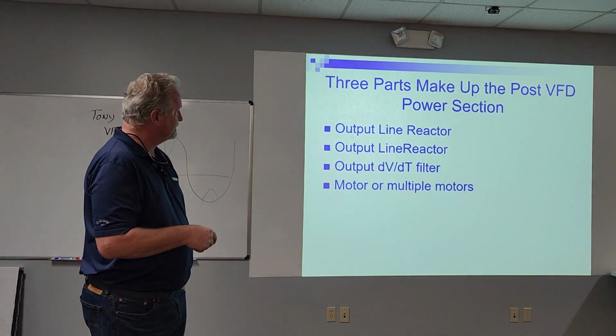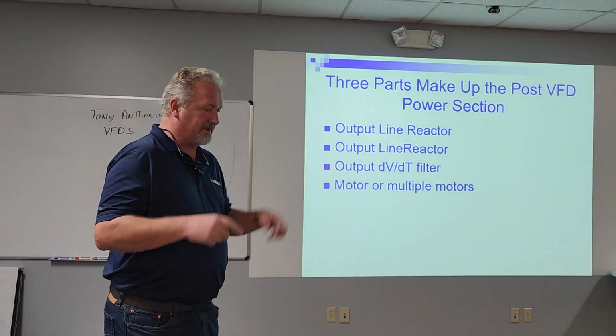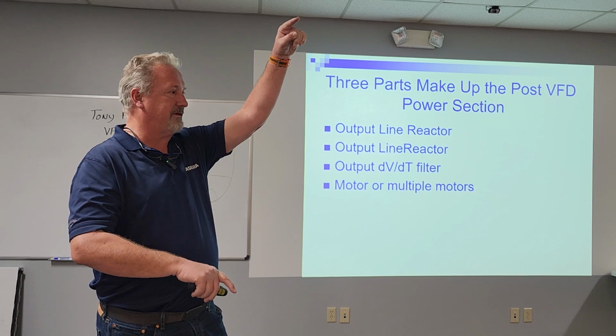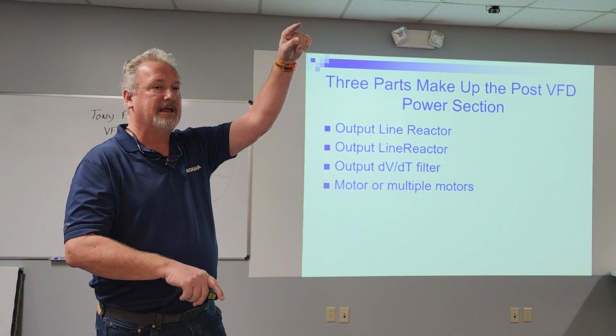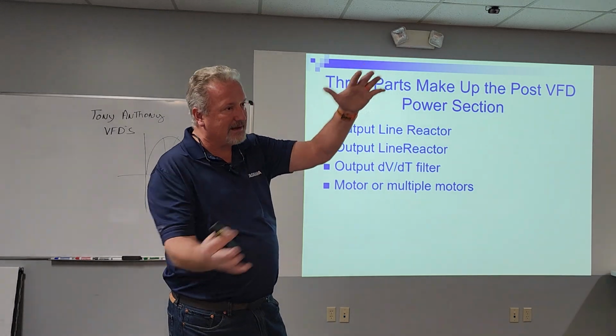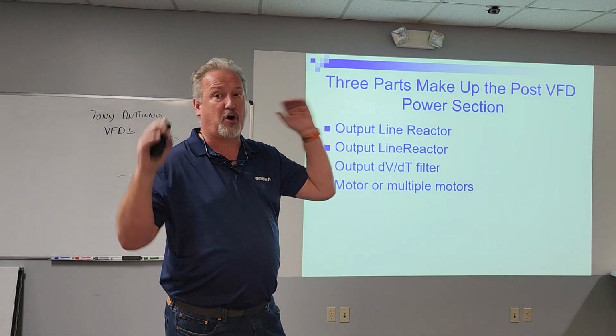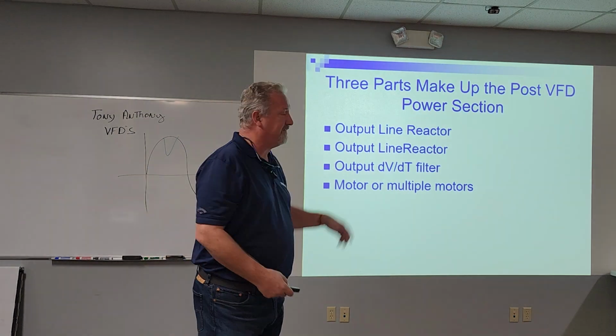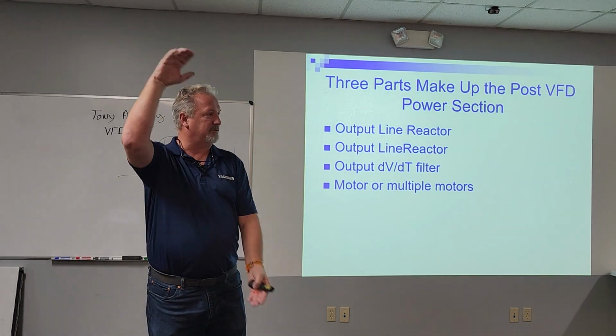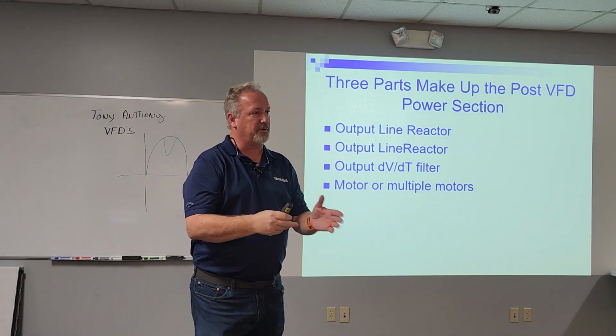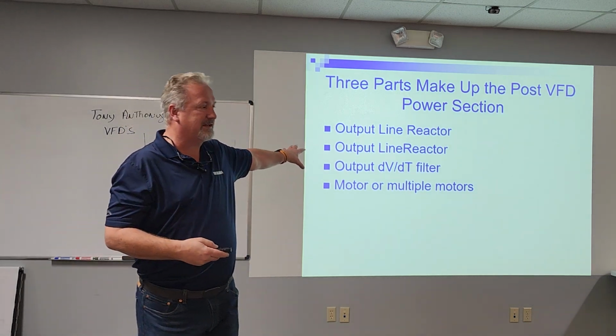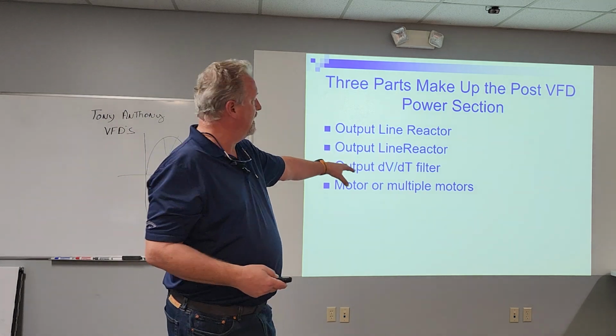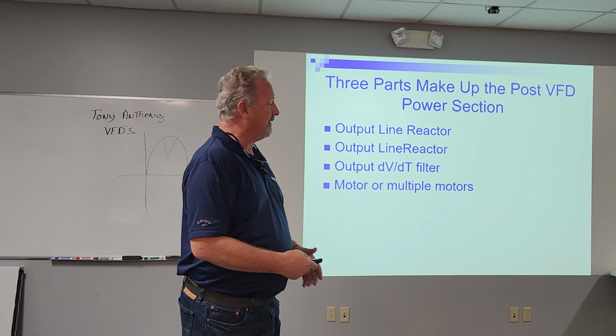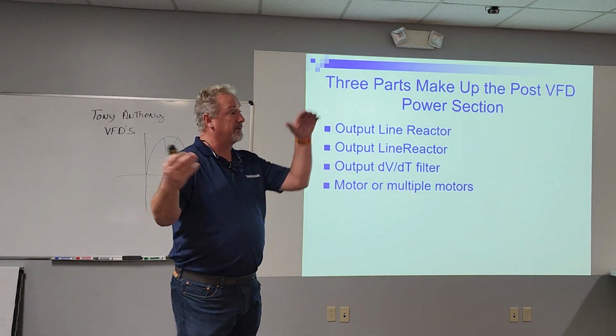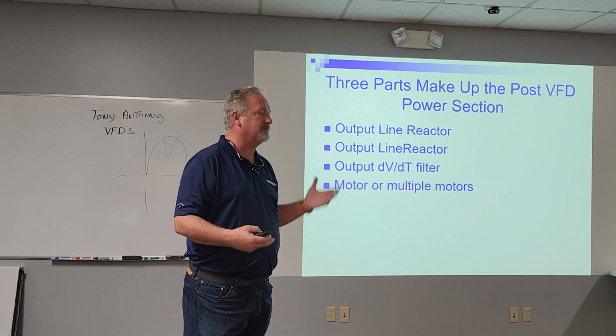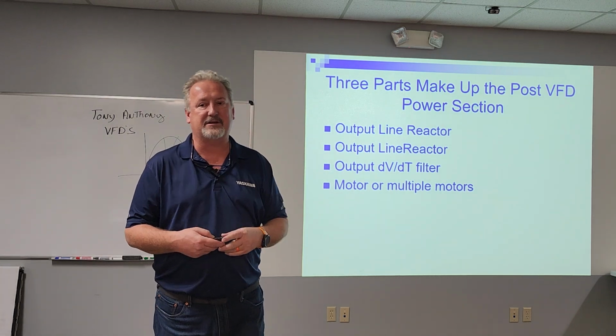We have dV/dt filters. Remember I said those spikes on the DC bus can be 1,500 volts peak to peak? Well, we use a line reactor, that'll squelch them down a little bit. But if we're still having trouble, or we're going like 700-800 foot, we'll put what's called a dV/dt filter, and that actually clips them and keeps them from growing. So it protects the motor. So if you get a certain distance, we may have to add what's called a dV/dt. That's differential voltage over time, and that's based off distance from the drive. The line reactor will protect the motor from those high spikes. So if you get out there a couple hundred foot, we'll throw in a line reactor. You get out there 400 or 500 foot, we may need to do a dV/dt filter.